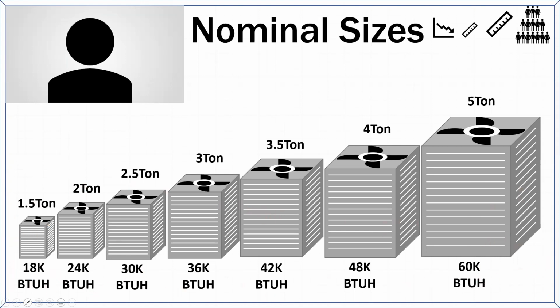And when they are off of these targets, they tend to be off on a fairly consistent basis, right? A modern 3-ton air conditioner in a particular climate is usually going to be in the same ballpark of BTUs, even from multiple manufacturers. So what's the problem here? Why is this such a big deal? Well, Manual S tells me that I should try to be within 15% of my load when I size the system, right?